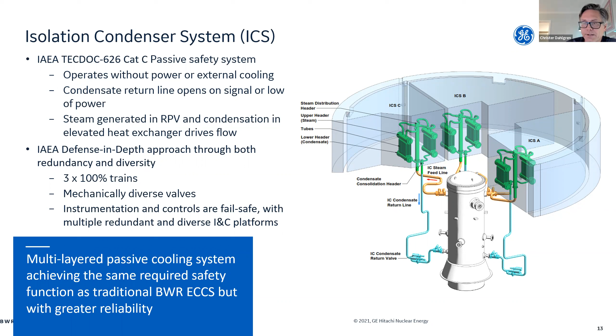It's 3 by 100. So each of these heat exchangers is 100% capacity for decay heat removal and overpressure protection. We have mechanically diverse valves on the return lines, and the instrumentation and controls is fail safe, with multiple redundant and diverse I&C platforms. So it's like a multi-layered passive cooling system which achieves the same required safety functions as the traditional boiling water reactor emergency core cooling system, but with much greater reliability. And I would also add, without any alternating current. We don't need any power supply to keep this design feature in place and keep the decay heat removal going.